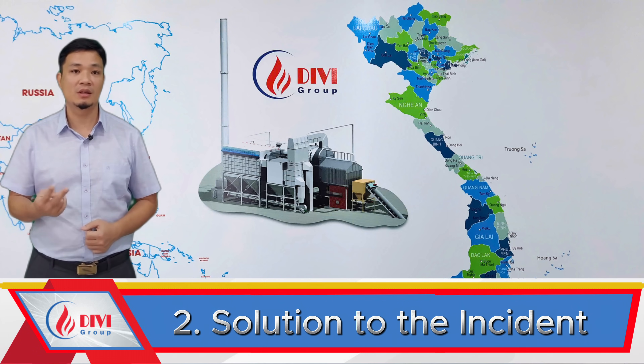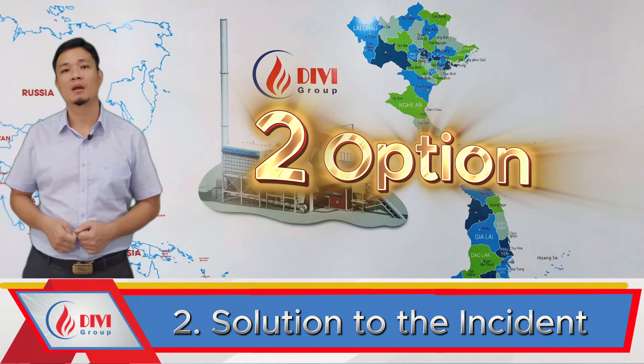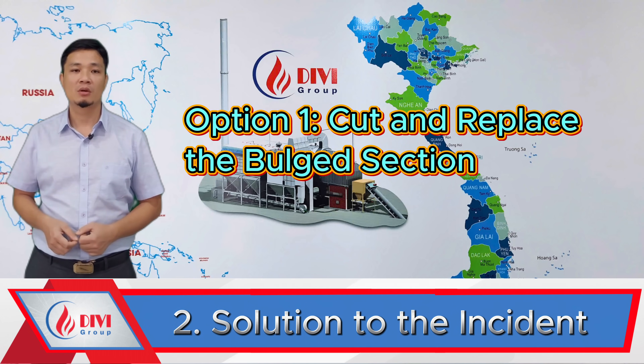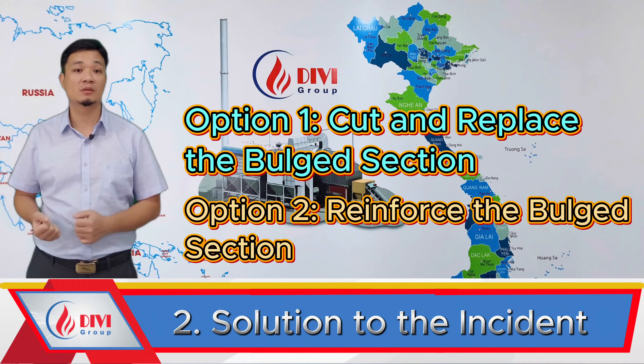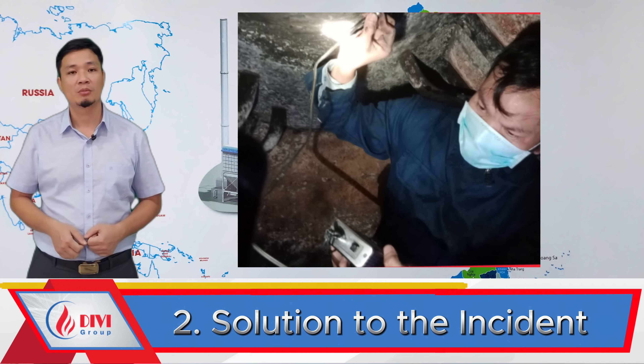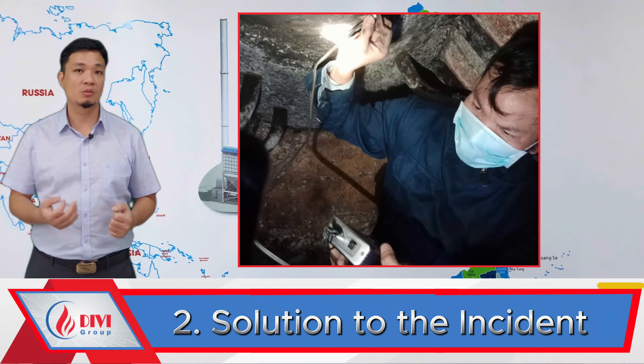That wraps up Part 1. Moving on to Part 2: how we fixed it. After receiving a request for support, DIVI conducted a site survey and proposed two solutions — Option 1: cut and replace the bulged section with new material; Option 2: reinforce the swollen section with local plate strengthening. To decide between these, we first performed ultrasonic thickness testing on the swollen drum wall.